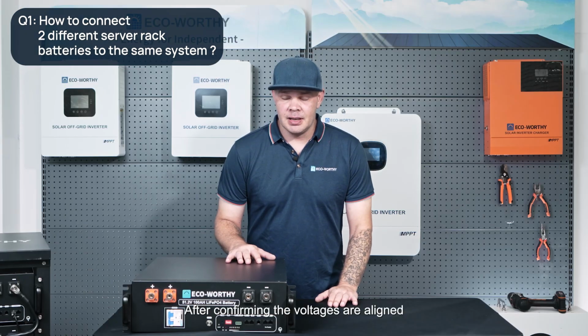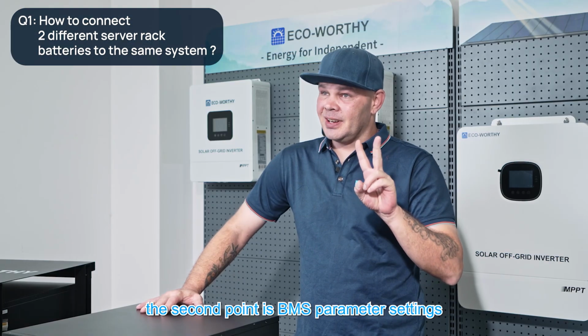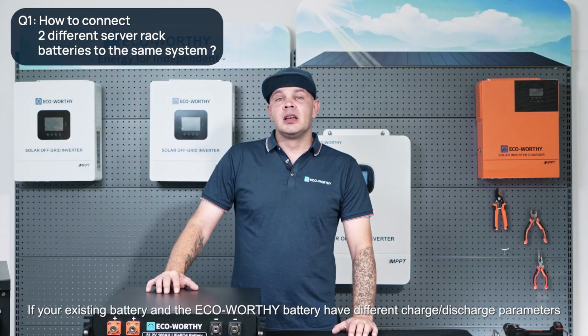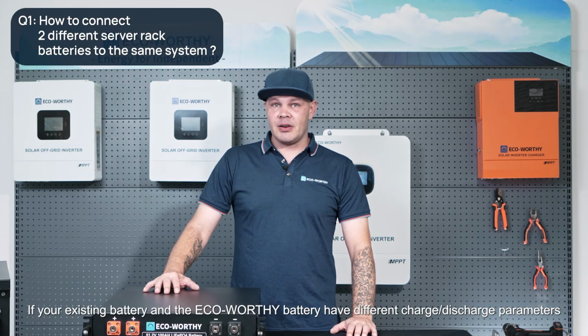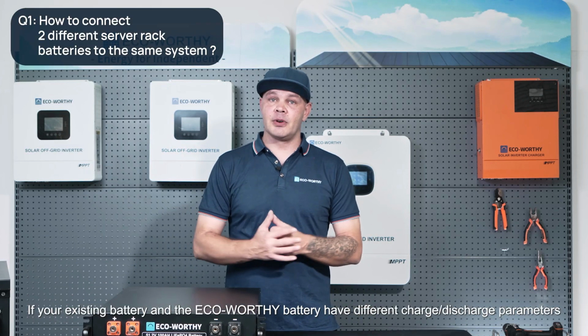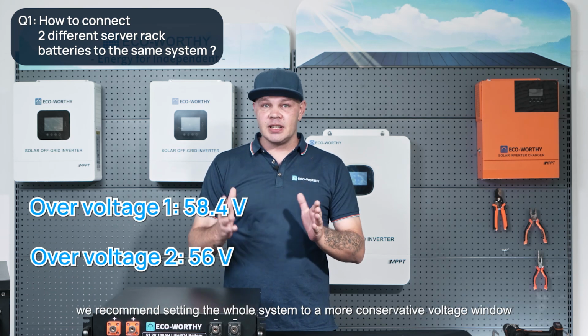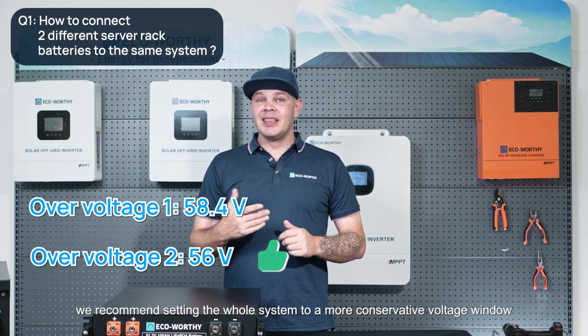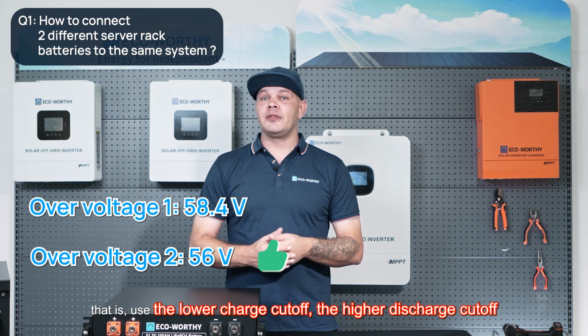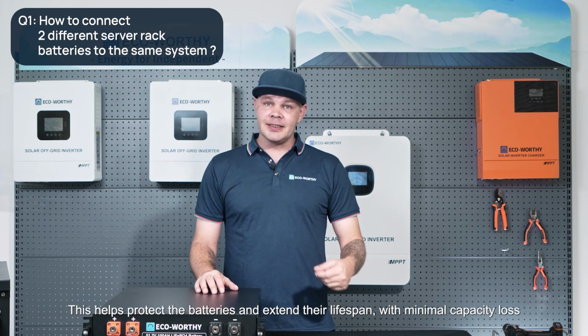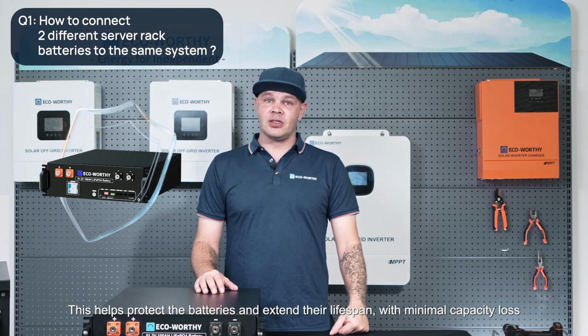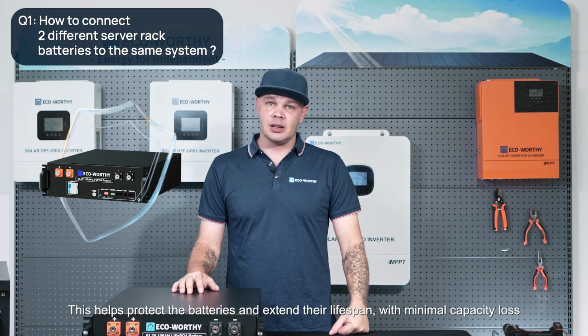After confirming that the voltages are aligned, the second point is BMS parameter settings. If your existing battery and the eco-worthy battery have different charge/discharge parameters, we recommend setting the whole system to a more conservative voltage window. That is, use the lower charge cutoff and the higher discharge cutoff. This helps protect the batteries and extend their lifespan with minimal capacity loss.